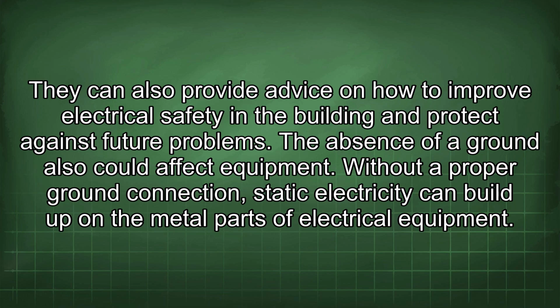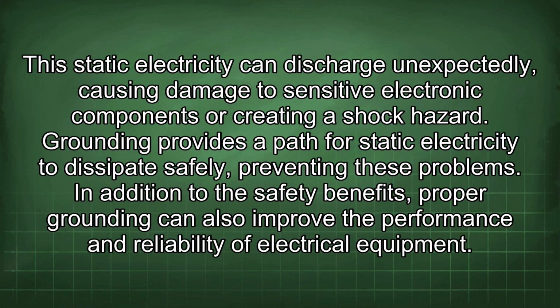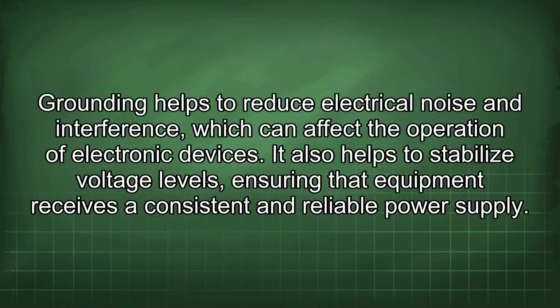The absence of a ground also could affect equipment. Without a proper ground connection, static electricity can build up on the metal parts of electrical equipment. This static electricity can discharge unexpectedly, causing damage to sensitive electronic components or creating a shock hazard. Grounding provides a path for static electricity to dissipate safely, preventing these problems. In addition to the safety benefits, proper grounding can also improve the performance and reliability of electrical equipment. Grounding helps to reduce electrical noise and interference, which can affect the operation of electronic devices. It also helps to stabilize voltage levels, ensuring that equipment receives a consistent and reliable power supply.